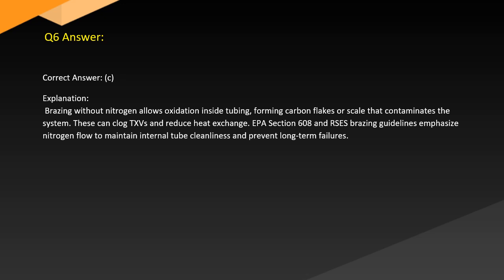Answer. Correct answer, C. Explanation. Brazing without nitrogen allows oxidation inside tubing, forming carbon flakes or scale that contaminates the system. These can clog TXVs and reduce heat exchange. EPA Section 608 and RSES brazing guidelines emphasize nitrogen flow to maintain internal tube cleanliness and prevent long-term failures.